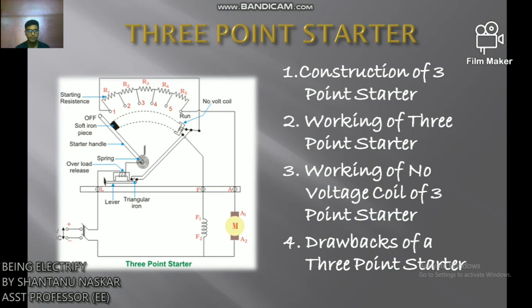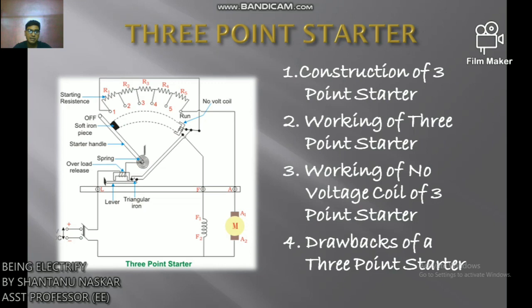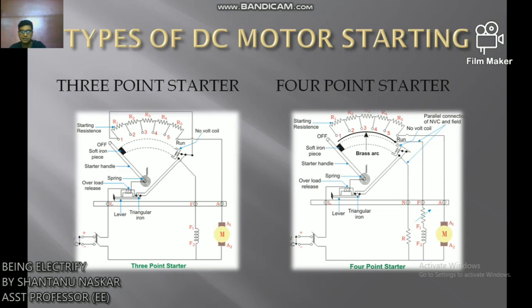A three-point starter is a device that helps in the starting and running of a DC shunt motor or compound wound DC motor, similar to a four-point starter. This type of DC motor requires a starter due to the presence of back EMF, which plays a critical role in governing the operation of the motor. The back EMF develops as the motor armature starts to rotate in the presence of the magnetic field by generating action, countering the supply voltage. At starting, the back EMF is zero.